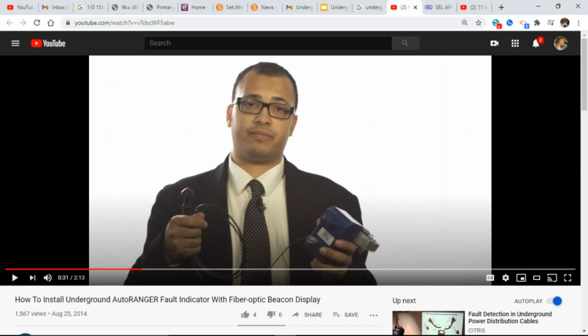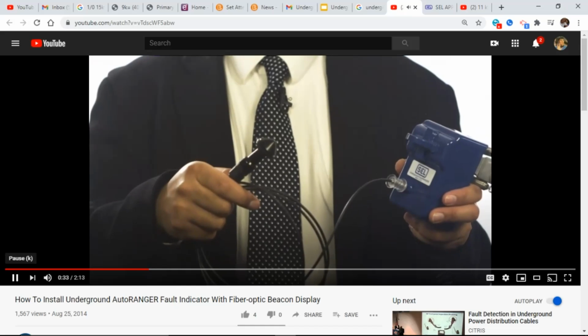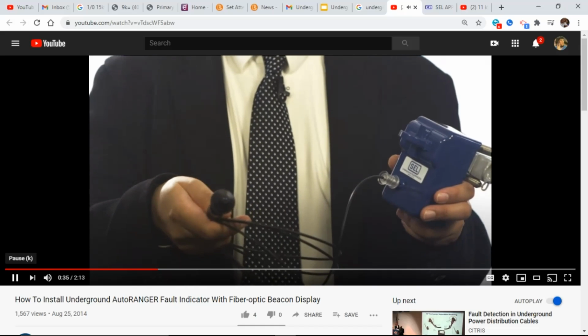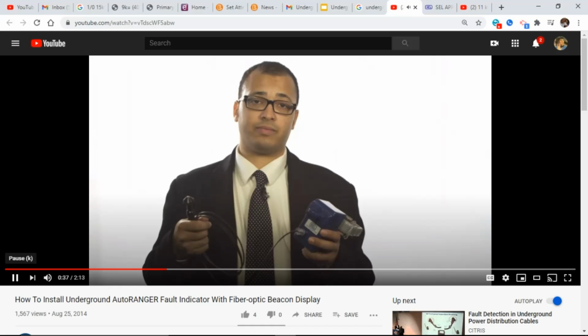You don't have to have, if you want to open the lid and see the little red flashing light here, you can. But I think this extra piece of equipment right here was an extra $5, $7. Go ahead and get that and mount it on your transformer. This remote fiber optic display allows you to easily troubleshoot for faults in the field from outside the enclosure.